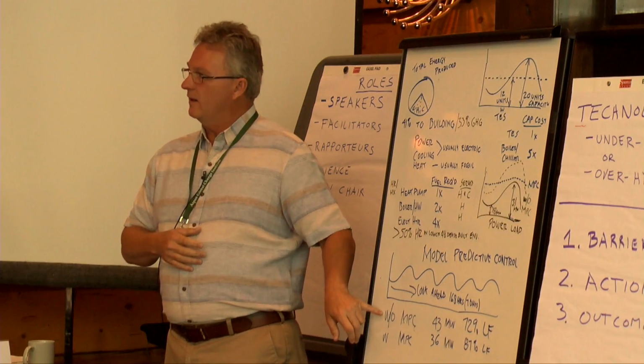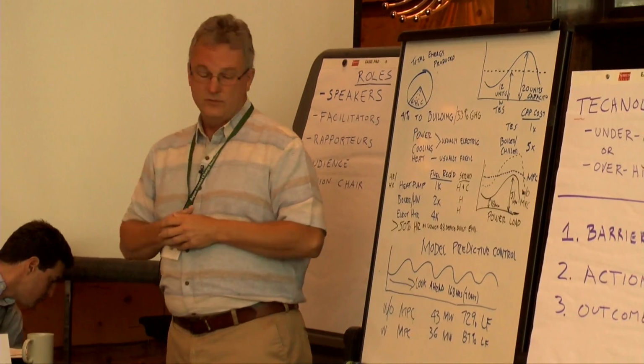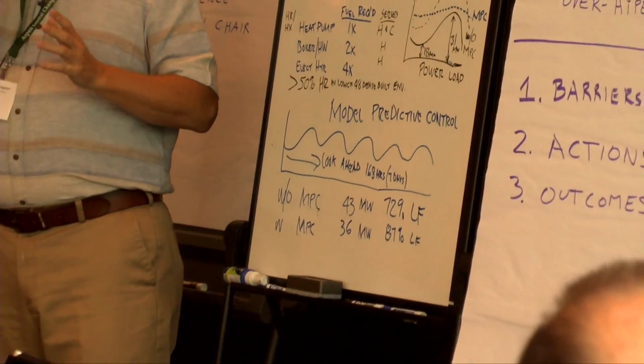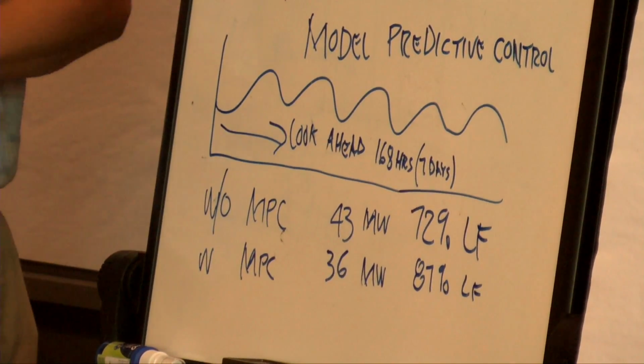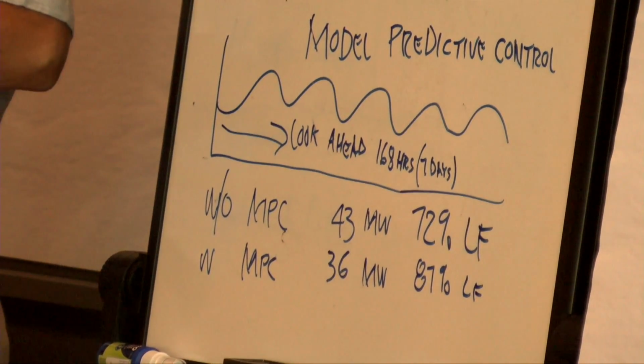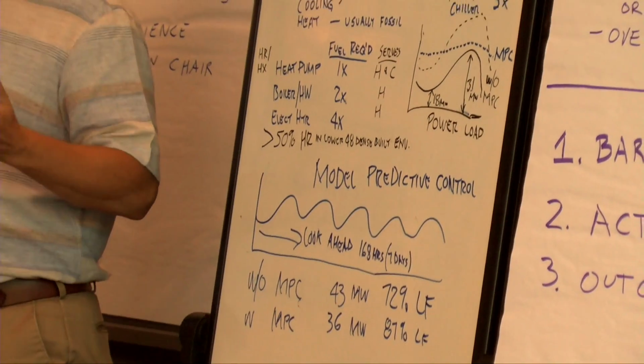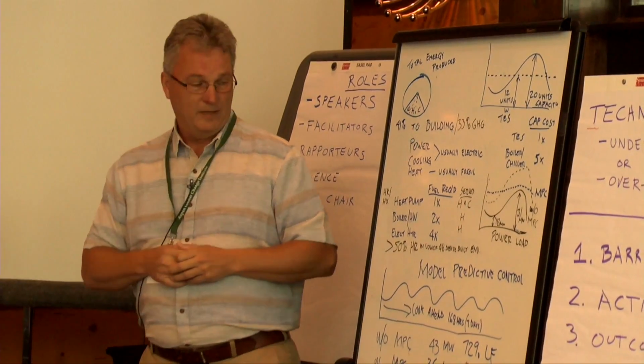What that program does, and we've proved this through a training exercise with our new system at Stanford, when we didn't have MPC and we just had our operators go through a sample year and show us how they would run the plant, we gave them a set of loads, 8760 loads of heating, power, and cooling, and said, starting from January 1 at hour 1, dispatch this. Show us every hour what you'd turn on, turn off, and take and put from thermal storage. And the results were that we normally have an 18 megawatt minimum load and 31 megawatt maximum background building electrical load on campus. So the additive work with humans dispatching, because this plant's about a 20 megawatt plant. If you turned everything on, it could draw 20 megawatts compared to the building load of 18 to 31 megawatts.